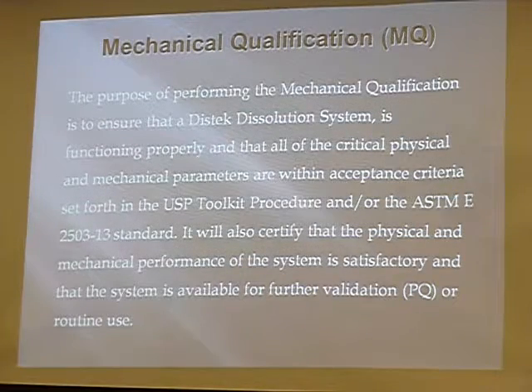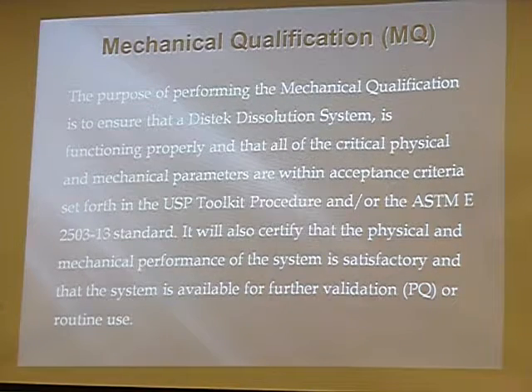The mechanical qualification. That's the biggie, that's the one that takes the longest. The purpose of performing mechanical qualification is to ensure that a Distek dissolution system is functioning properly and that all the critical physical and mechanical parameters are within acceptance criteria set forth in the USP toolkit procedure and/or the ASTM E2503-13 standard. I don't know what regulations monitor what you do in the countries that you're servicing your equipment at, but we all perform by USP standards here in the United States, and we use the USP toolkit procedure and/or the ASTM.